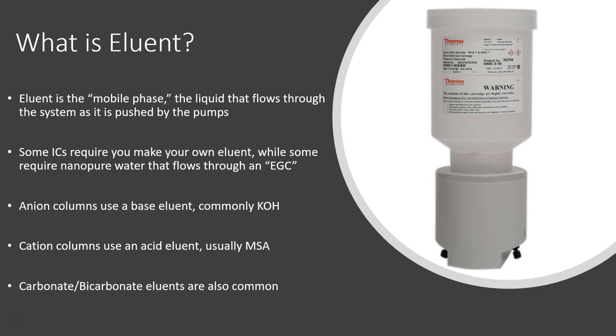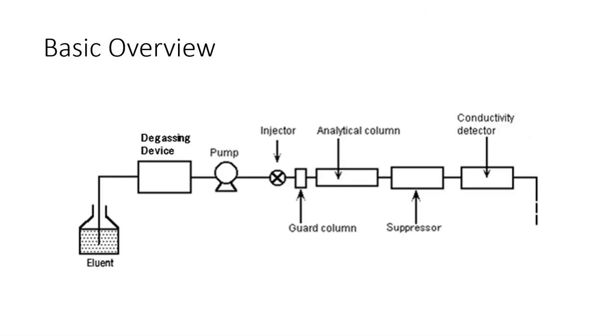Anion columns use a base eluent which is usually potassium hydroxide, and cation columns use an acid eluent which is usually methane sulfonic acid. You may hear the term carb-bicarb systems—that's because carbonate and bicarbonate eluents are also very common with IC. Back to this image, we see that our eluent is pushed through the system by the pumps. It goes through a degassing device which removes gas because we don't want any air bubbles getting into our system.